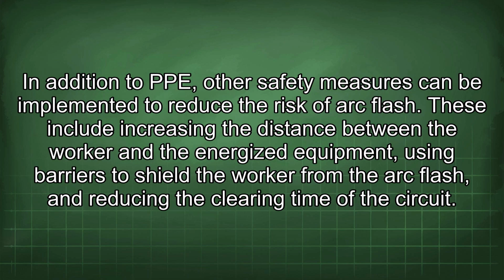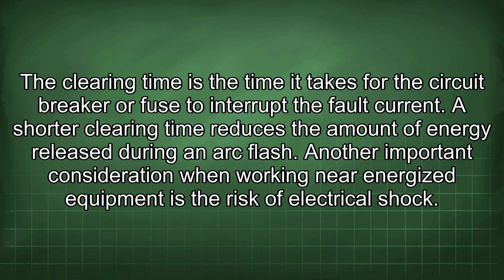In addition to PPE, other safety measures can be implemented to reduce the risk of arc flash. These include increasing the distance between the worker and the energized equipment, using barriers to shield the worker from the arc flash, and reducing the clearing time of the circuit. The clearing time is the time it takes for the circuit breaker or fuse to interrupt the fault current. A shorter clearing time reduces the amount of energy released during an arc flash.